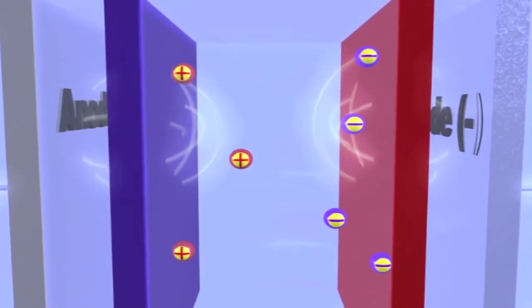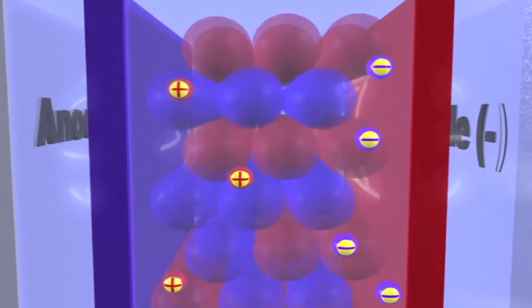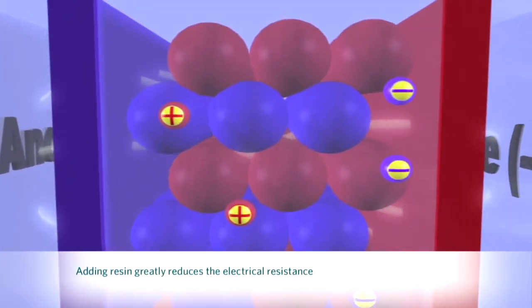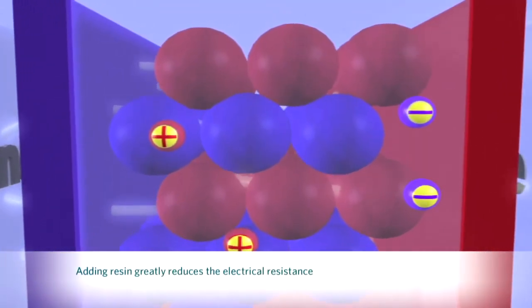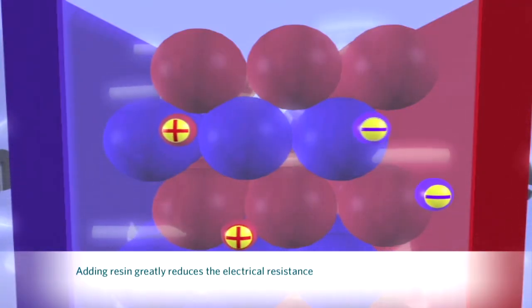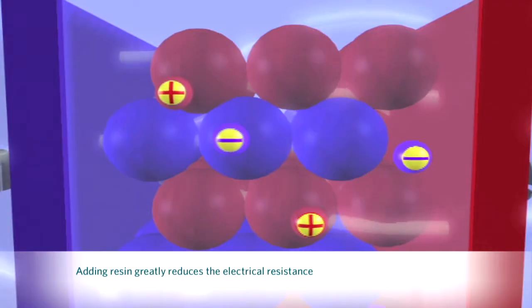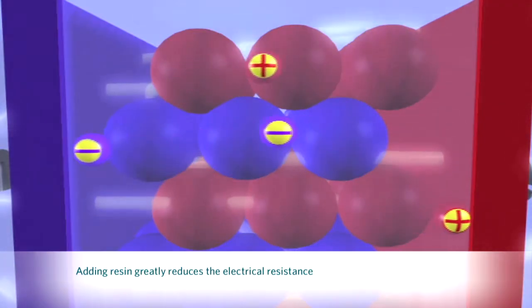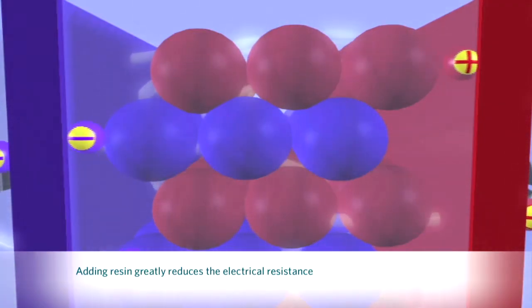IonPure's CEDI technology solves this problem by sandwiching a mixture of cation and anion-selective resins between the two membranes. The large surface area, now offered by the resin beads, effectively eliminates the ion diffusion resistance and allows the ions to move freely, even in ultra-pure water solution.